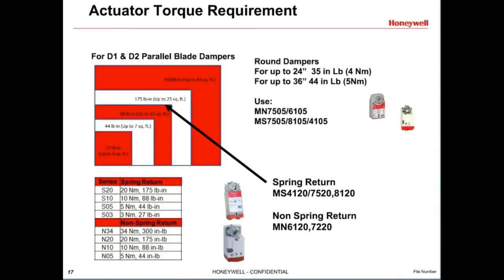For round dampers, 35 inch-pounds is sufficient torque for up to 24 inch diameters, and 44 inch-pounds for up to 36 inches. So most installers use a 44 inch-pound 5 Newton-meter actuator on all round dampers, such as the MN7505 non-spring return modulating, or MS8105 spring return 2-position 24 volt actuator. For large dampers, sometimes it is necessary to use more than one actuator to provide enough torque to operate the damper, in which case extra hardware should be used, such as a tandem mounting kit.